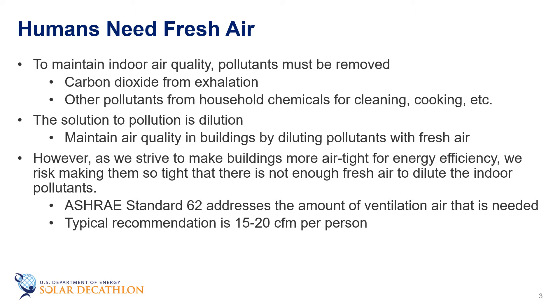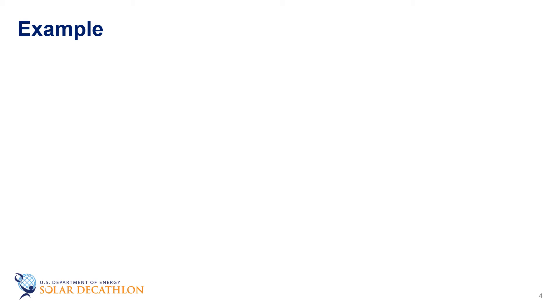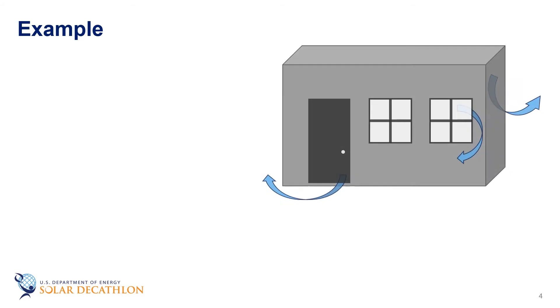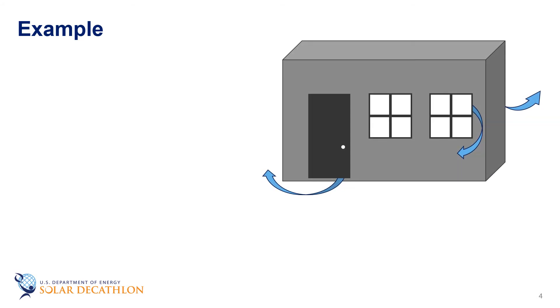Typically, the recommendation is somewhere around 15 to 20 cubic feet per minute per person. While that might only apply for when a person is in the space, some amount of ventilation should be provided when the building is not occupied. As an example, let's look at a sample building that we looked at in other episodes. We had specified an air exchange rate of 0.2 air changes per hour, or ACH.